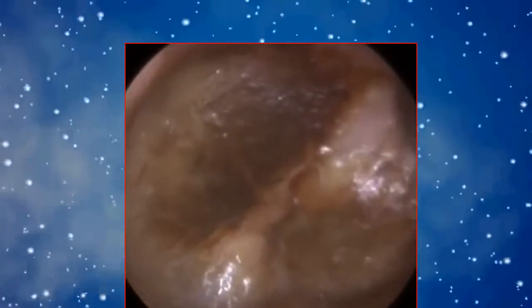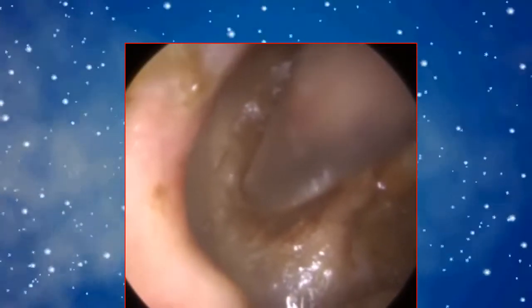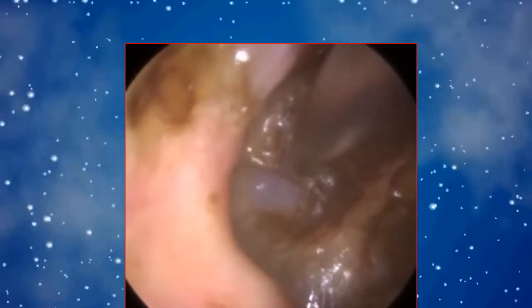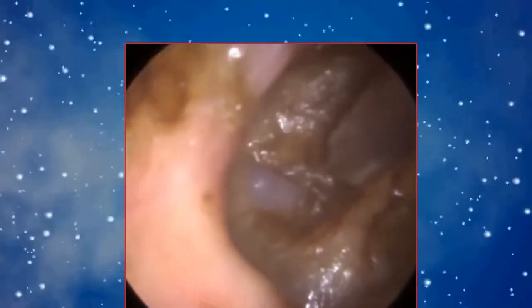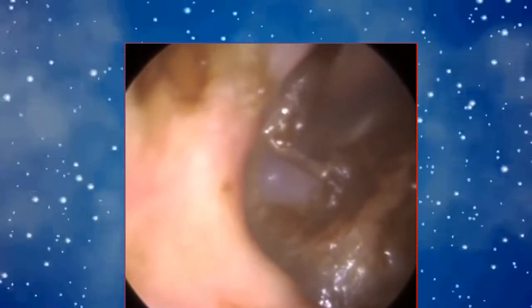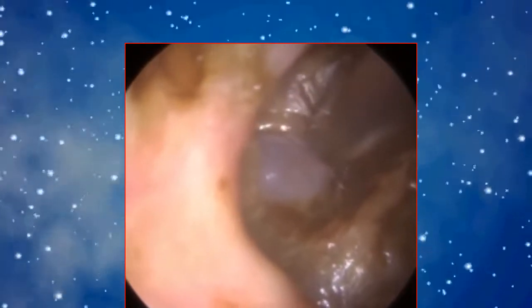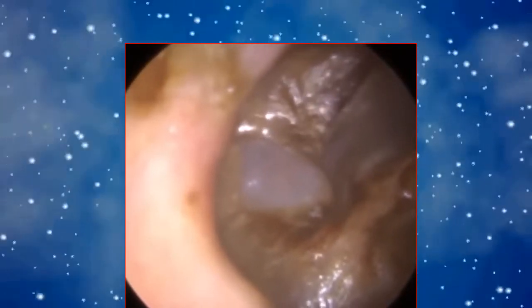So the endoscope itself, the rod lens system, so think about an endoscope like a telescope. You've got a series of lenses, rod lenses, sequentially adjacent to each other, which gives you the image. And then coating these rod lenses are a series of fibre optics, bundles of fibre optics. And this transfers light into the ear, and it also helps bring the image back. And the fibre optics, because they coat the entire length of the rod lens system of an endoscope, they add a slight bit of heat, and this heat then helps prevent fogging.